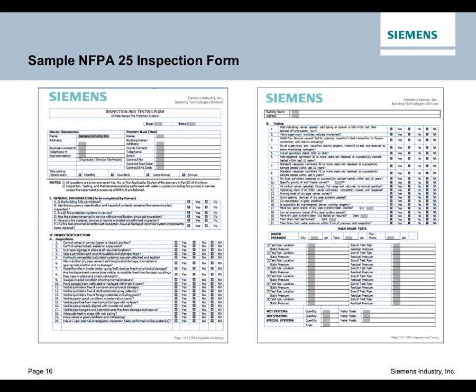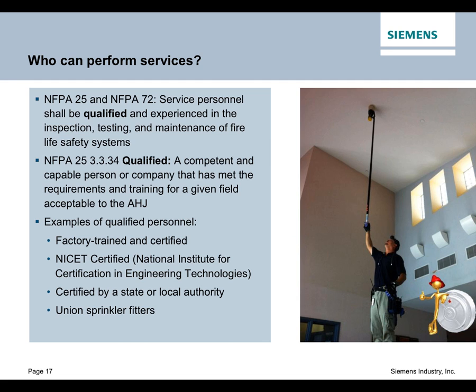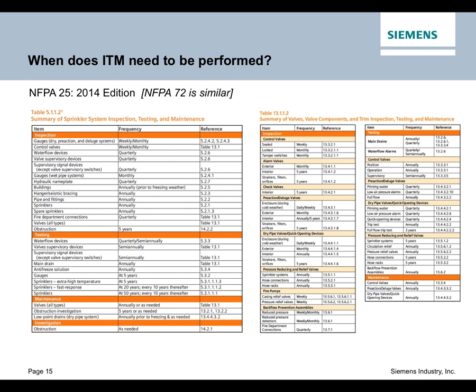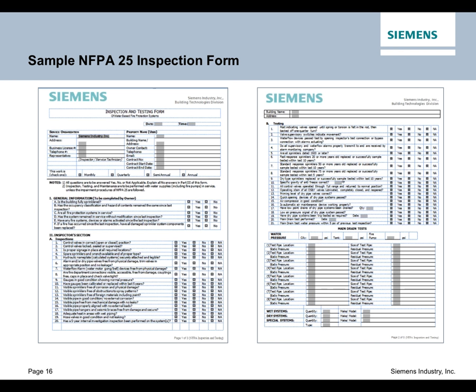And let's talk about that differentiation. The concept of inspection really means visual. That means you can walk around the building, look at that sprinkler valve, and make sure that that valve is open. That would qualify for an inspection. You can inspect the gauge on a sprinkler system. You can inspect the smoke detector in a building to make sure that there are no obstructions, that it's there, and that it looks like it's operating correctly.